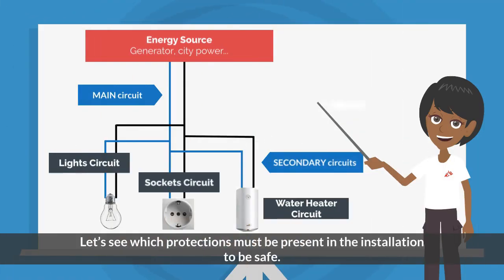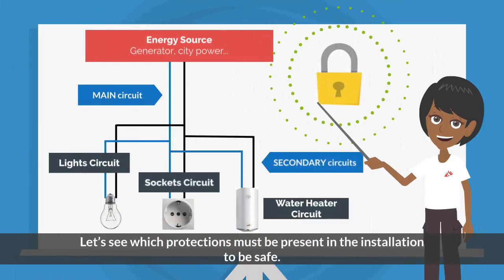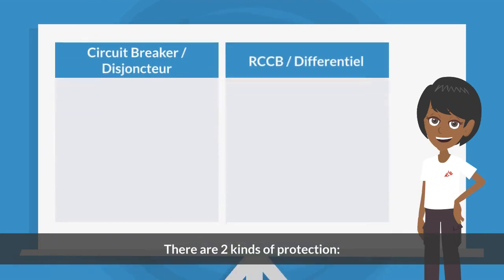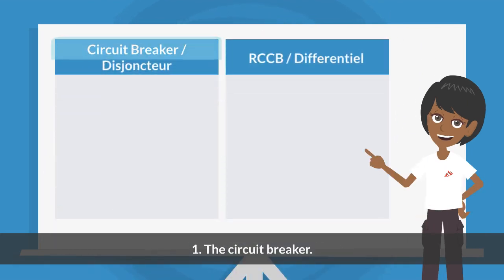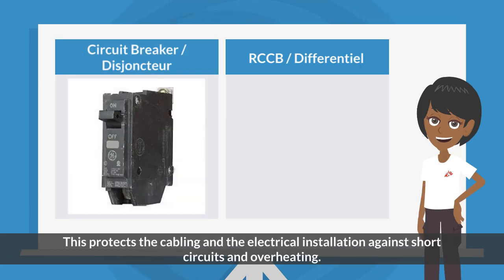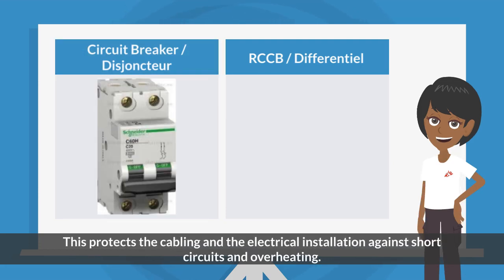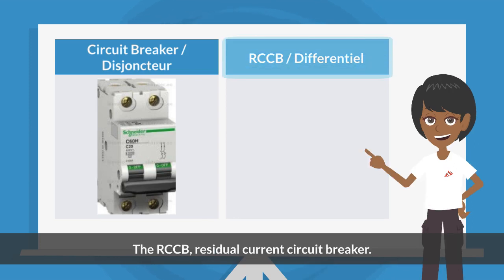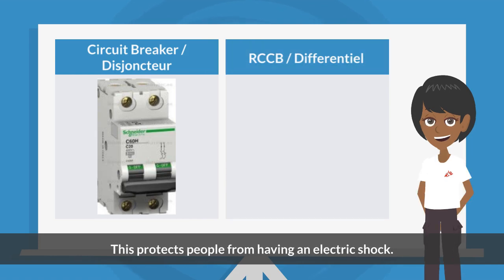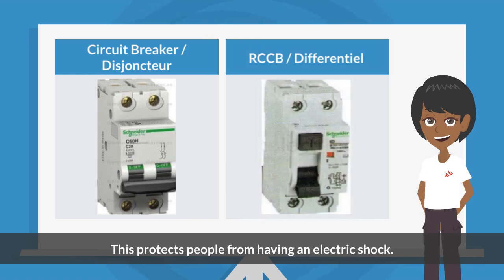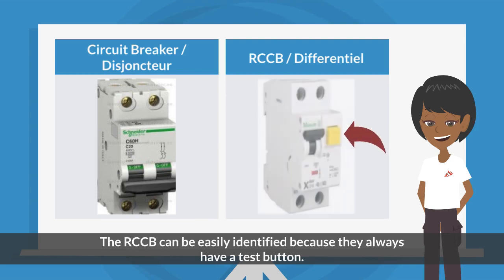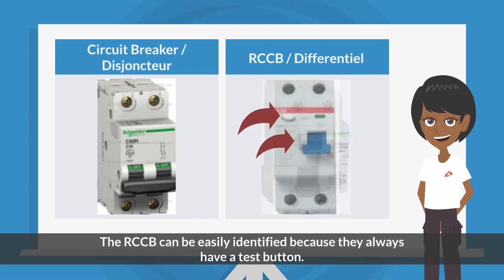Let's see which protections must be present in the installation to be safe. There are 2 kinds of protection. 1. The circuit breaker. This protects the cabling and the electrical installation against short circuits and overheating. 2. The RCCB, residual current circuit breaker. This protects people from having an electric shock. The RCCB can be easily identified because they always have a test button.